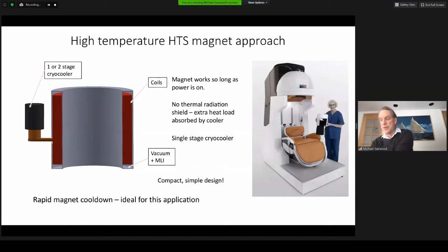As compared to a normal MRI magnet, our high temperature superconducting magnet has a very simple internal configuration. A solid state cryocooler is bolted directly to the superconductor coils and by conduction, the coils are cooled. There is no need for a thermal radiation shield since the cryocooler absorbs any heat. On the right is a mock-up of the MRI scanner. Hopefully you can appreciate how this system will improve user experience as compared to standard MRI whereby the subject must lie inside a long tube.